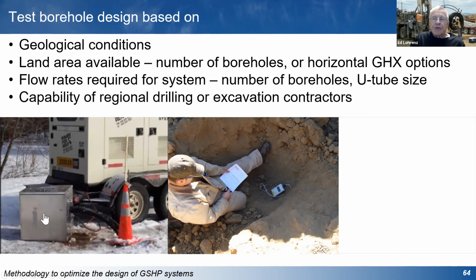We also know roughly how many boreholes we're going to require and what the total water flow through the ground heat exchanger is going to be, and that's going to help determine the size of the pipe, whether you want to use 1 inch pipe or 1.25 or 3/4 inch pipe, based on the number of boreholes that you have space for and the most cost-effective drilling depth. So we can design the borehole and locate it where it can easily be integrated with the final borehole design, designed in such a way that it can fit in with the right pipe size and everything else.